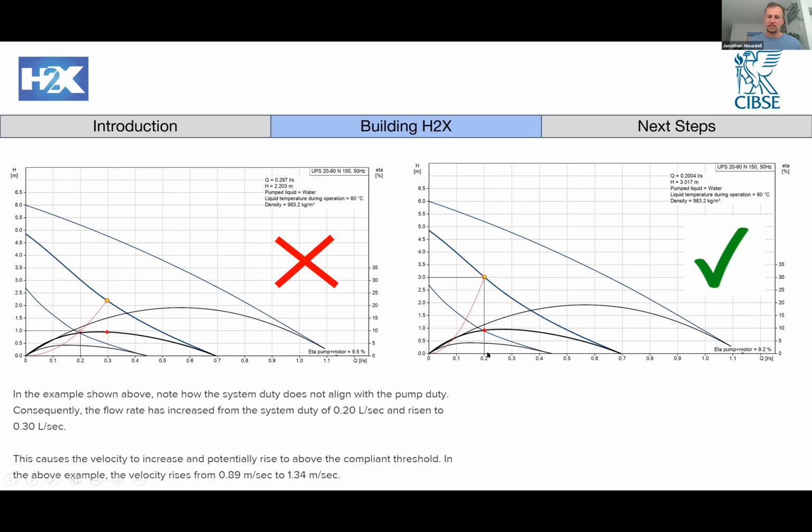It's not a well-known issue in the industry, but I suppose Grundfos are obviously aware of it because they get called out to site a lot. So they were more than happy to partner with us. And that means that we now have the Grundfos pumps in the software, and in the code we've got the 3 different pump settings, which is pump setting 1, 2, and 3.